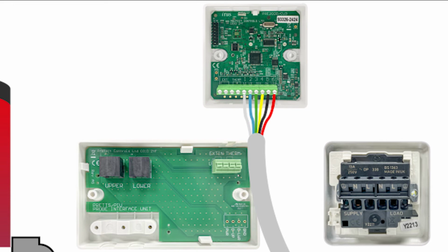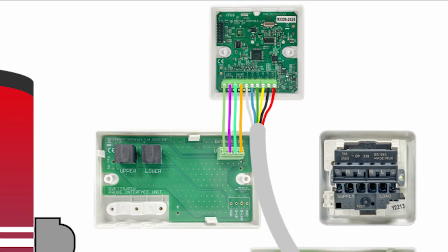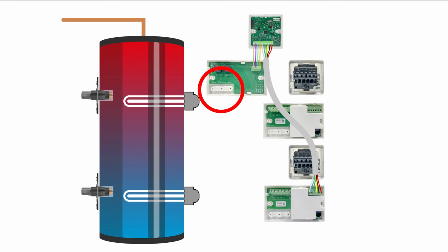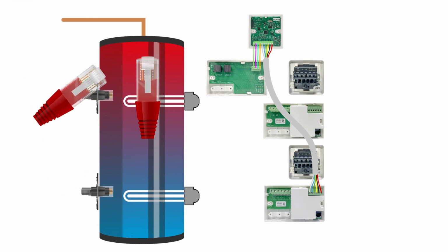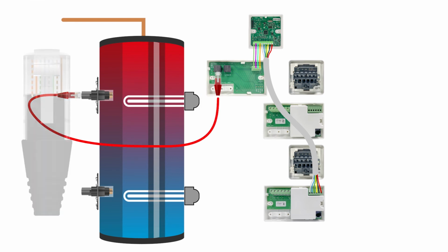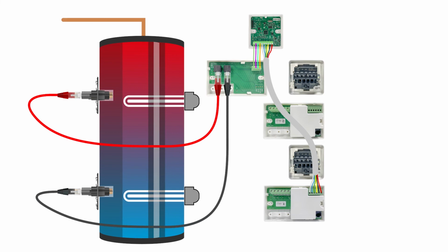Use low-voltage alarm cable to connect the control unit to the probe interface unit. Connect the EXT terminal on the probe interface unit to the EXT terminal on the control unit. Likewise, the therm terminal on the probe interface unit is connected to the therm terminal on the control unit. Remove the knockouts on the base of the probe interface unit. Use the red RJ45 patch lead to connect the upper probe to the probe interface unit, and the black RJ45 to connect the lower probe. Secure the cables with the clamp on the probe interface unit.